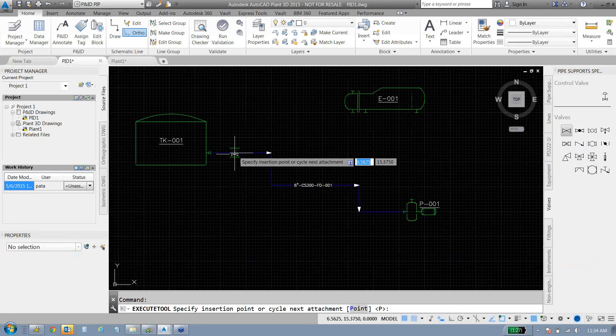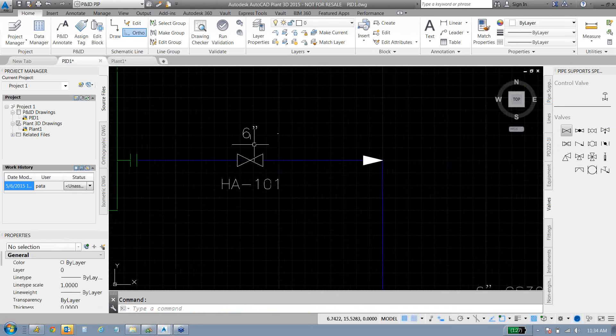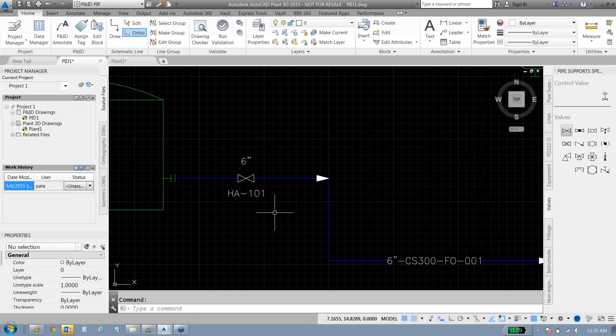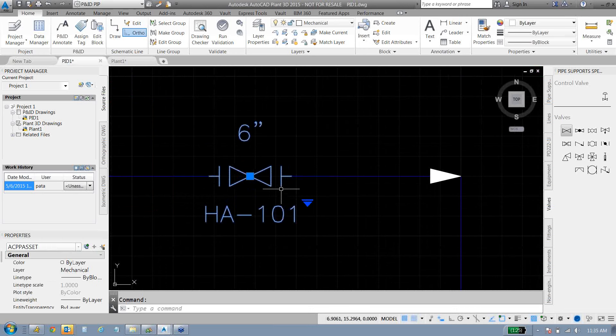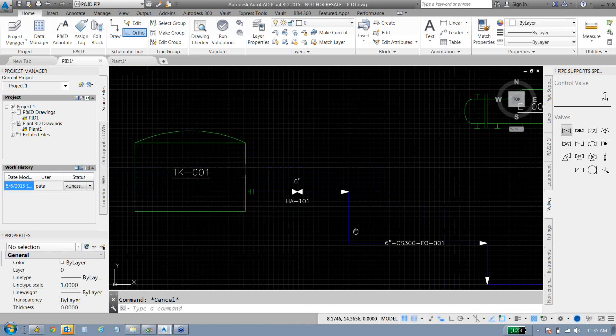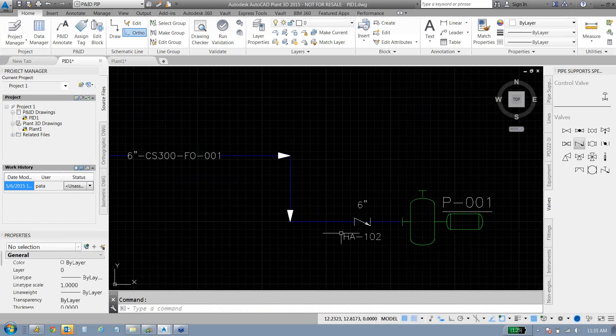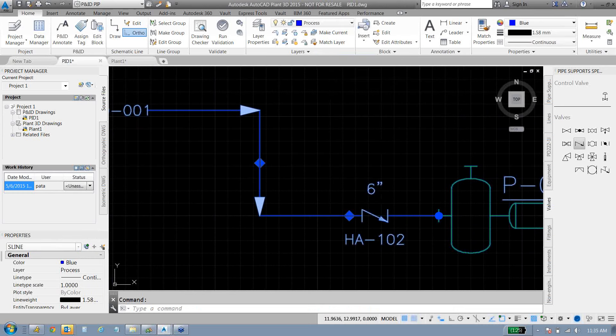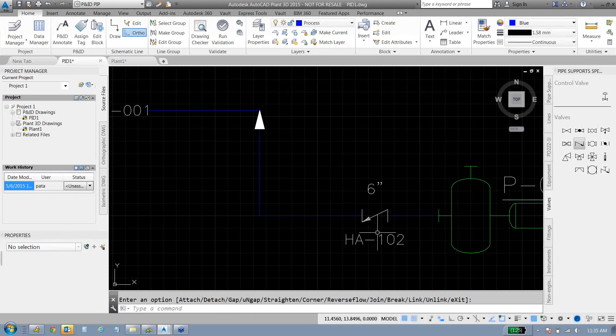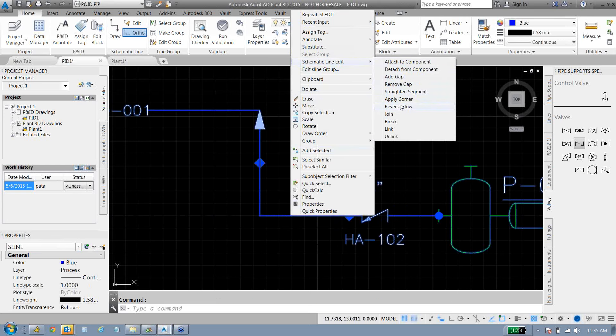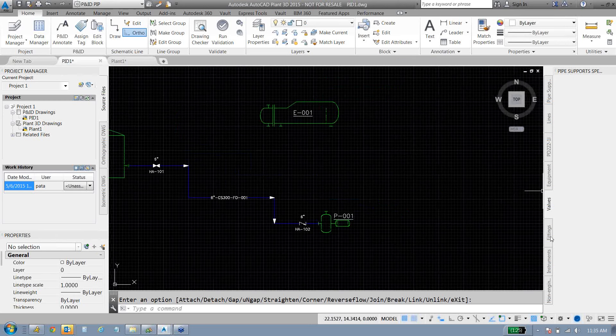After the line, I'll throw a valve here. You can see my valve automatically will get its line size from the line. It will automatically be tagged in a standard order, starting with 101 and going up. I can change the end connections of my valve. If I want some flanges on the end or if I want to make this a normally closed valve, I can just do that through the right-click menu. And you can see with certain valves, they are flow dependent. If I edit the line and reverse the flow of it, you can see that the check valve reverses with it.